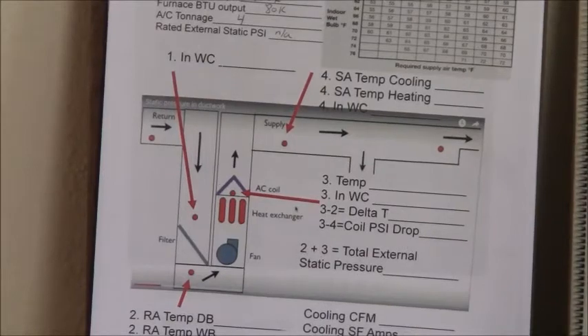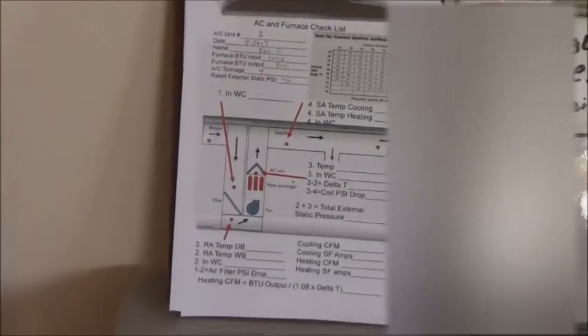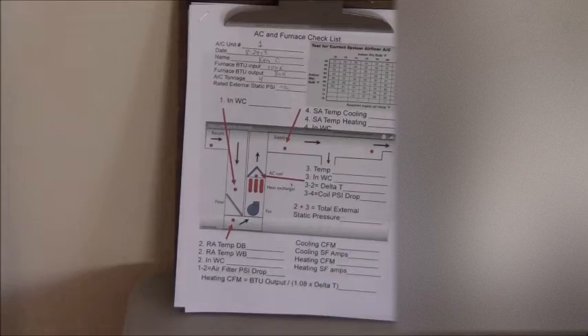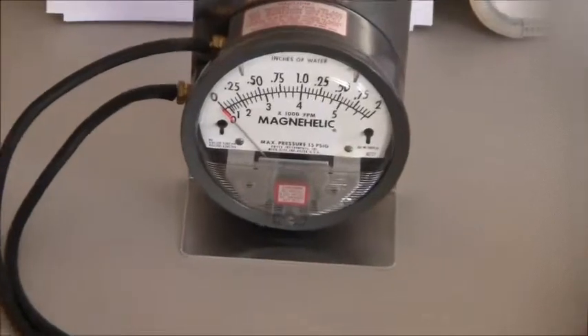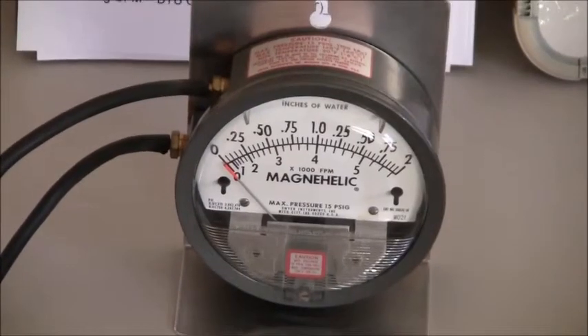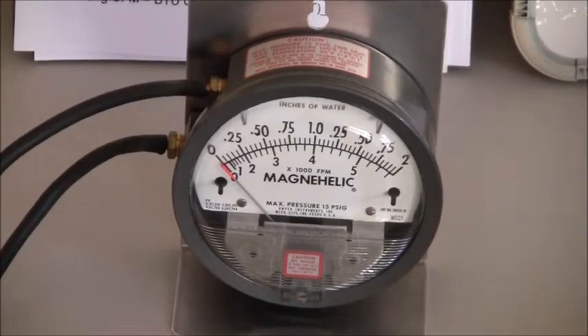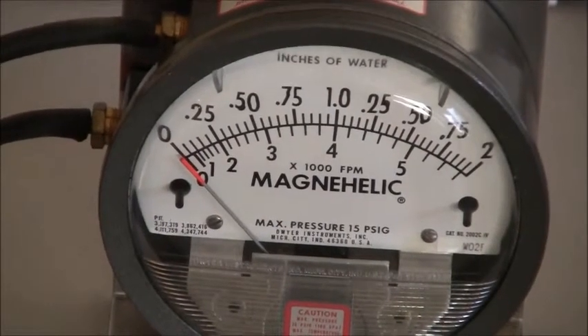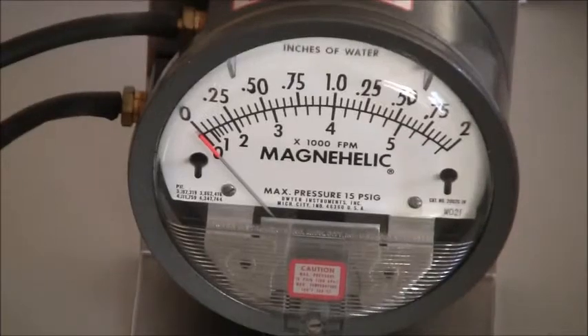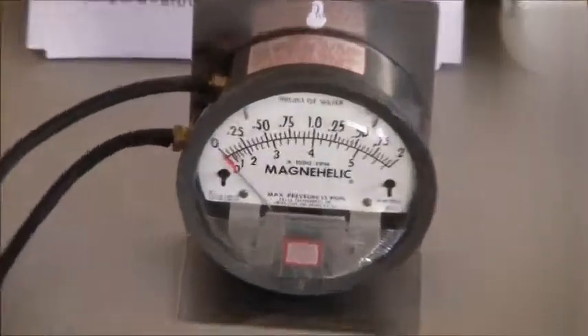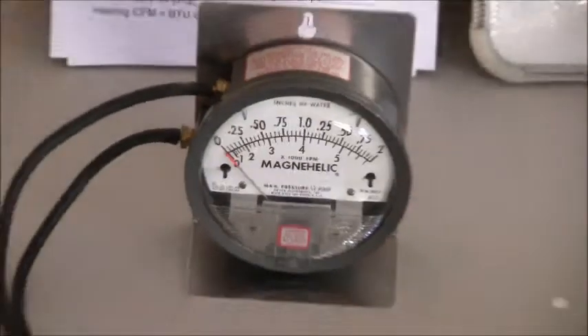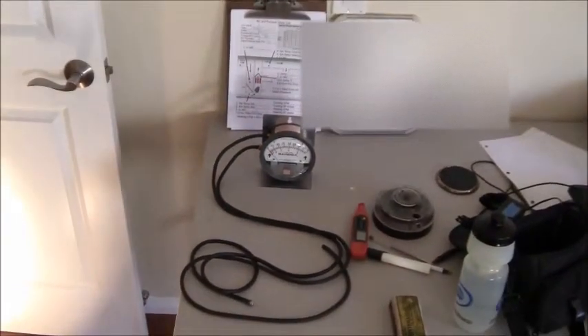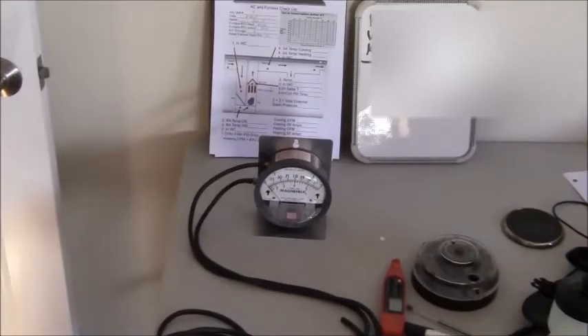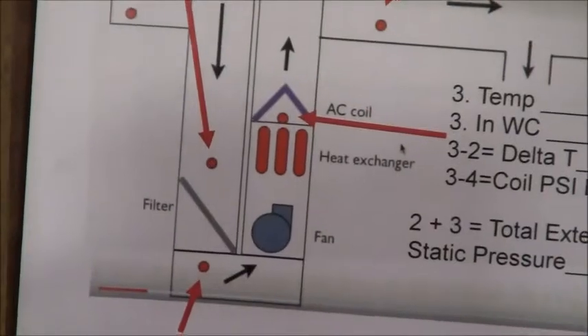So we're going to do sample readings with a magnehelic gauge. This here is a magnehelic gauge that I have. Luckily I did not have to purchase it, I already had one. This one goes all the way from 0 to 2 inch, but in reality you could just use 0 to 1 inch. But if I was going to purchase one, I would not purchase one of these. What I would purchase is one of the new digital ones. This one's 20 years old, so I just happen to have it, and that's why we're going to use it. And that is how we're going to fill in this information, and as I go through the system, I'll show you that.